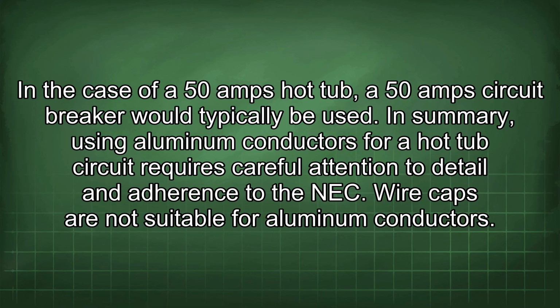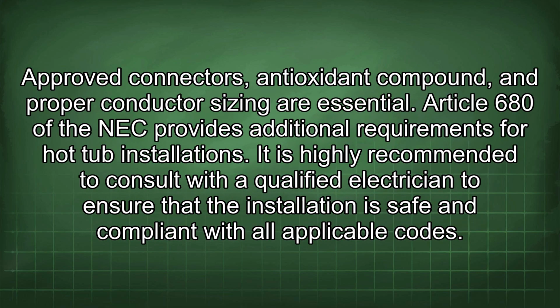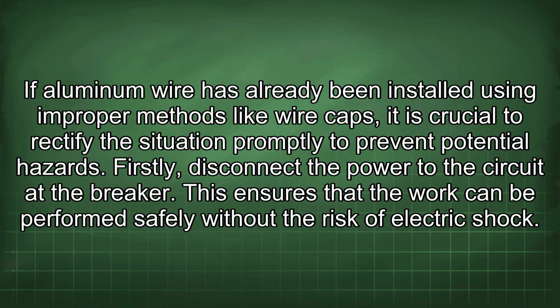Wire caps are not suitable for aluminum conductors. Approved connectors, antioxidant compound, and proper conductor sizing are essential. Article 680 of the NEC provides additional requirements for hot tub installations. It is highly recommended to consult with a qualified electrician to ensure that the installation is safe and compliant with all applicable codes. If aluminum wire has already been installed using improper methods like wire caps, it is crucial to rectify the situation promptly to prevent potential hazards.